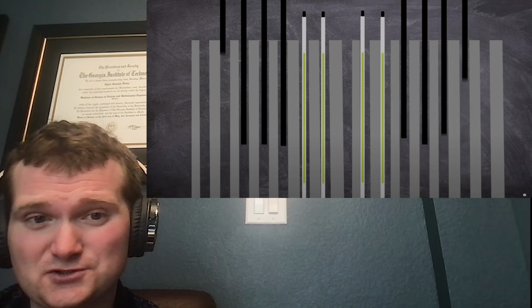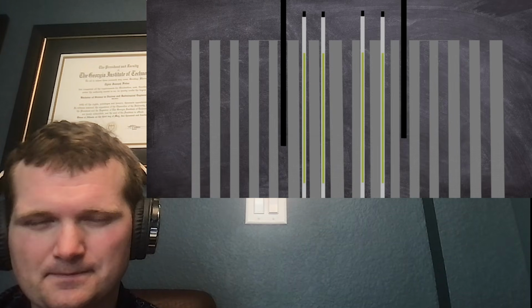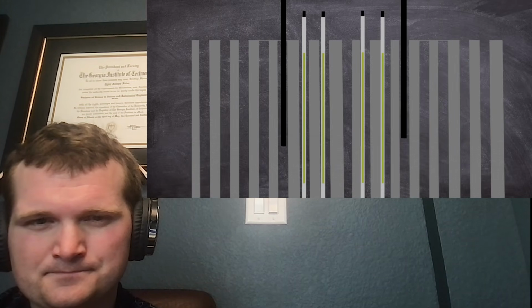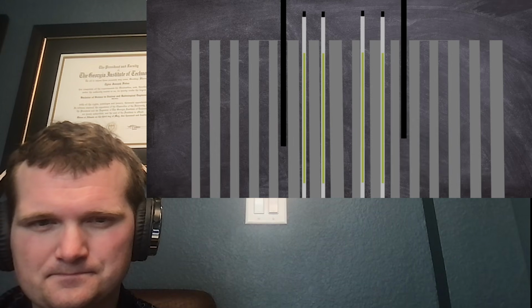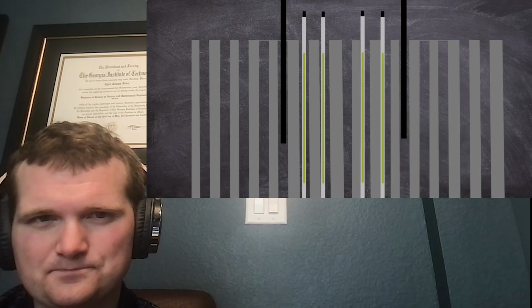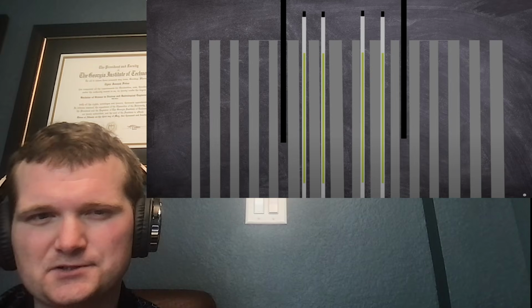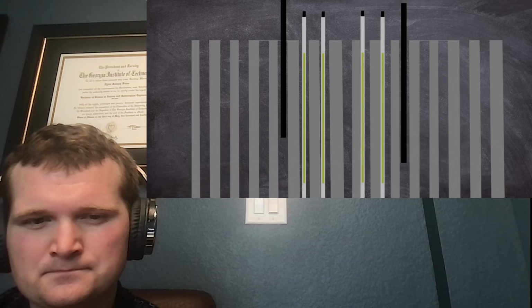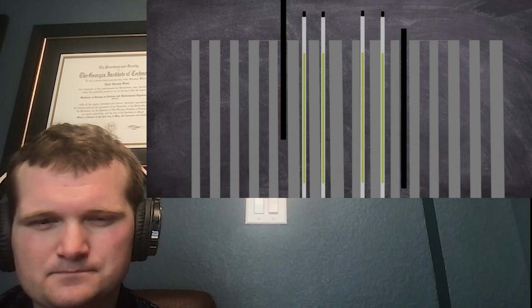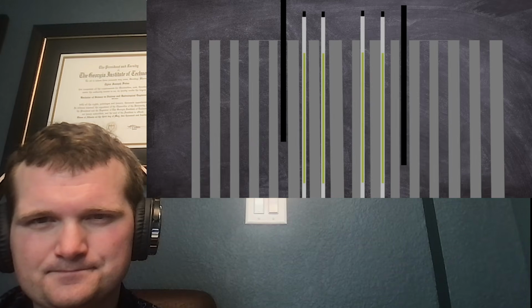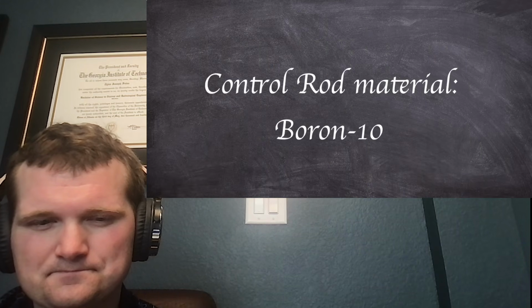And during a reactor trip, an emergency shutdown, and they all insert, it's going to shut down the reactor really, really fast, in a matter of a couple of seconds. During normal operations, the safety rods were held out of the reactor core, ready to be used in the event of a scram. Scram is another word for reactor trip. Out of the two main controls, only one was used for major regulating of the reactor's power, with the other being used for shimming, i.e. fine-tuning. All the rods were of a poison-type design employing enriched boron-10.